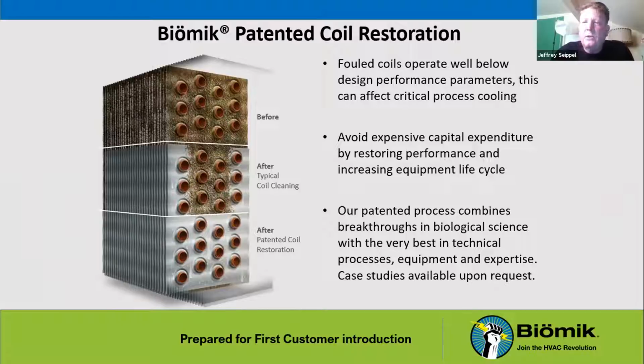These structures are made to have a lot of surface area in a very small space. So they're ripe for biological activity. You add water, you add organic material in the air, and you have biofilm. So previously, the top section of the cross section there, you can kind of see how a biofilm will take up residency in the whole surface area of the coil.